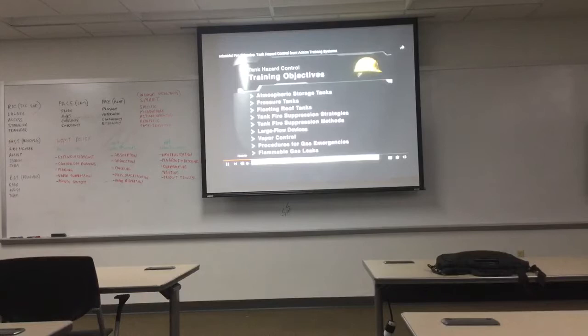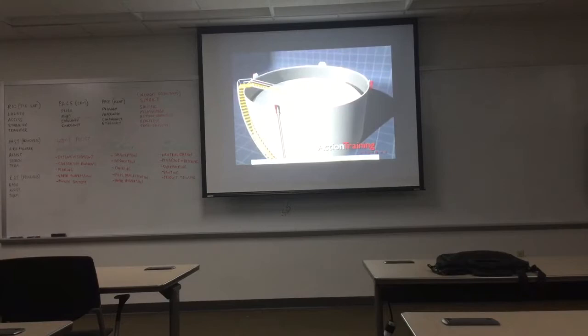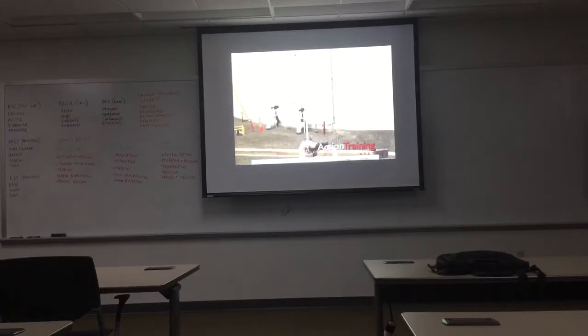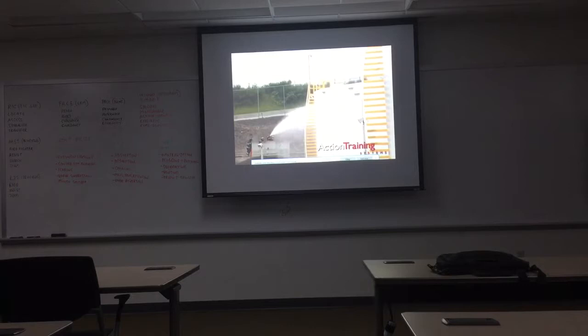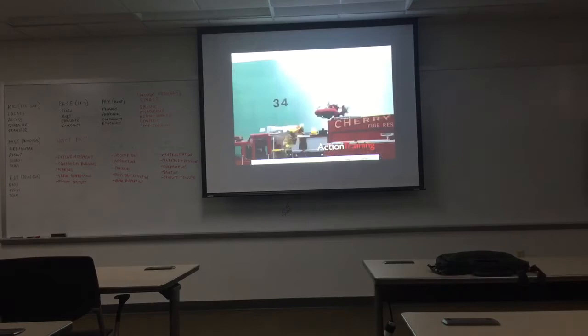Welcome to this sample course from Action Training Systems. All learning objectives of the course are listed on screen, and you will be shown a sample of these sections. Rim seal fires are the most common type of fire in open top floating roof tanks. When a fixed foam system is not installed or is not functional, this type of fire can be extinguished by extending foam hand lines up the roof access stairway to the gauger's platform. For rim seal fires in internal floating roof tanks, deploy the fixed system if one is available; if not, apply foam through the vents in sufficient quantities to extinguish the fire. When fighting rim seal fires in any tank with a floating roof, care must always be taken to avoid tilting or sinking the roof.